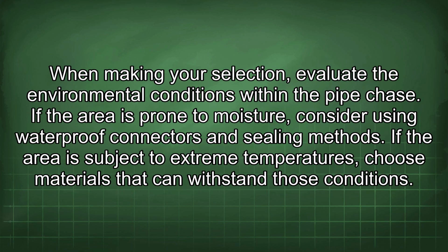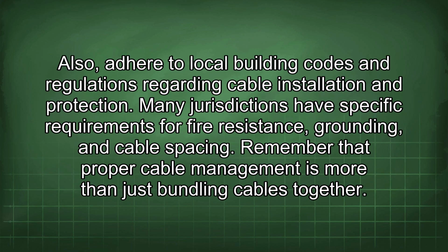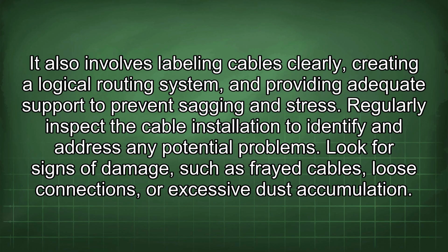When making your selection, evaluate the environmental conditions within the pipe chase. If the area is prone to moisture, consider using waterproof connectors and sealing methods. If the area is subject to extreme temperatures, choose materials that can withstand those conditions. Also, adhere to local building codes and regulations regarding cable installation and protection. Many jurisdictions have specific requirements for fire resistance, grounding, and cable spacing. Remember that proper cable management is more than just bundling cables together. It also involves labeling cables clearly, creating a logical routing system, and providing adequate support to prevent sagging and stress.